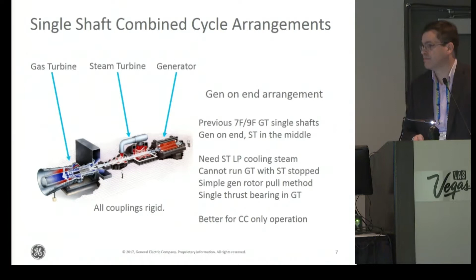This is the configuration GE did with some of their later F classes, particularly in Europe, what we called at the time the 9FB, which had the gas turbine on one end, the generator in the middle, and the steam turbine on the other end. That solved the issue of long axial expansion from the thrust bearing, because now the steam turbine can have its own thrust bearing, with a flex coupling between the steam turbine and the generator. But one problem this causes is having the generator in the middle.